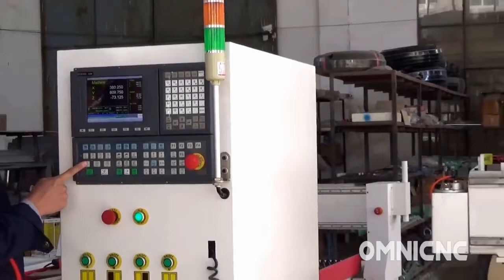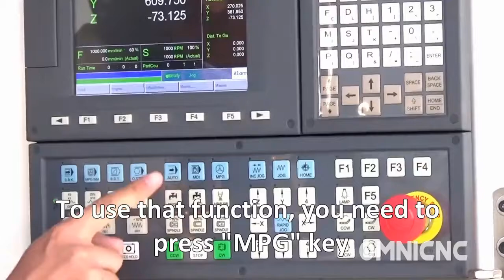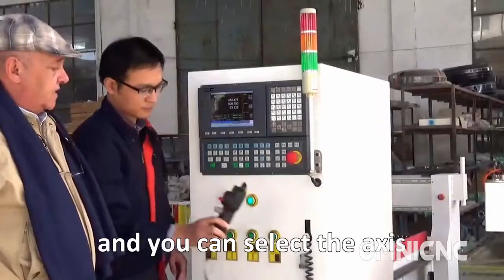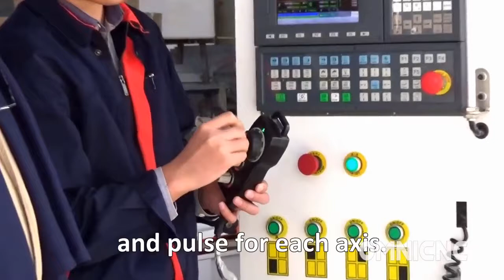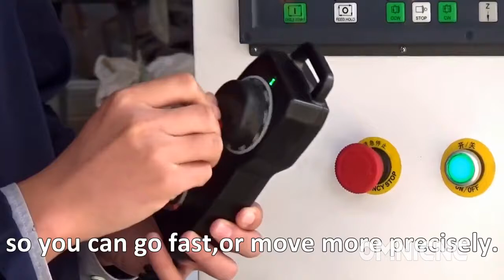Now there is another very useful type of moving. This is called the manual moving, and it's done by the manual pulse generator, this device over here. To use that device, you need to depress the MPG key. Then you can select the axis and the pulses per revolution for each axis, so it can go fast or move in more precise way. In between 1/10 of a millimeter per pulse or 1/1000 of a millimeter per pulse for each axis. This is very useful when setting the height of the tool.